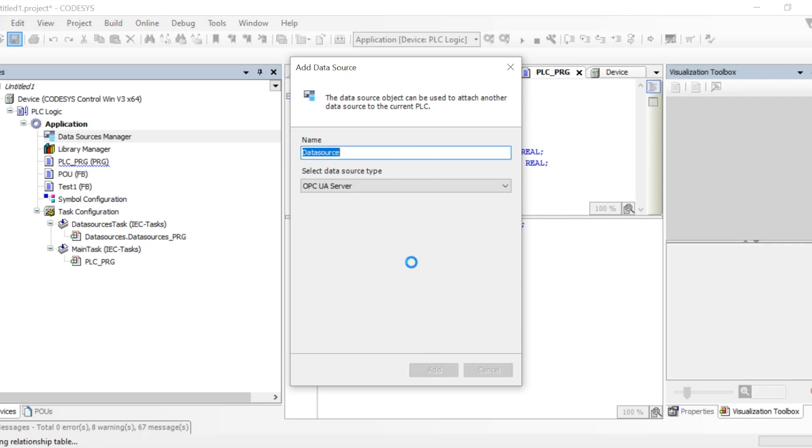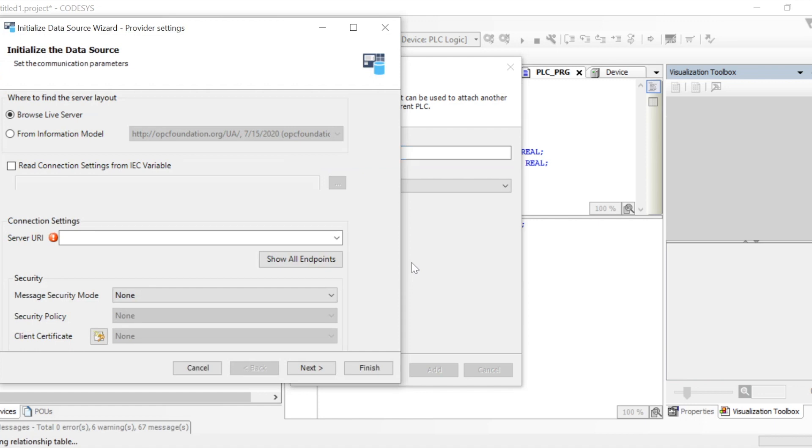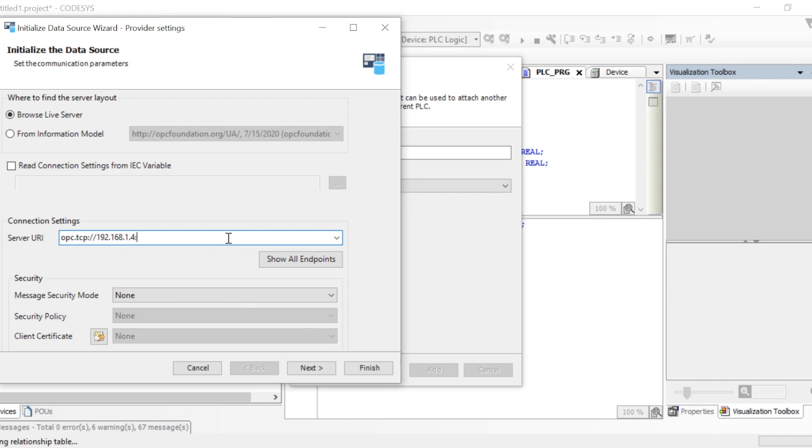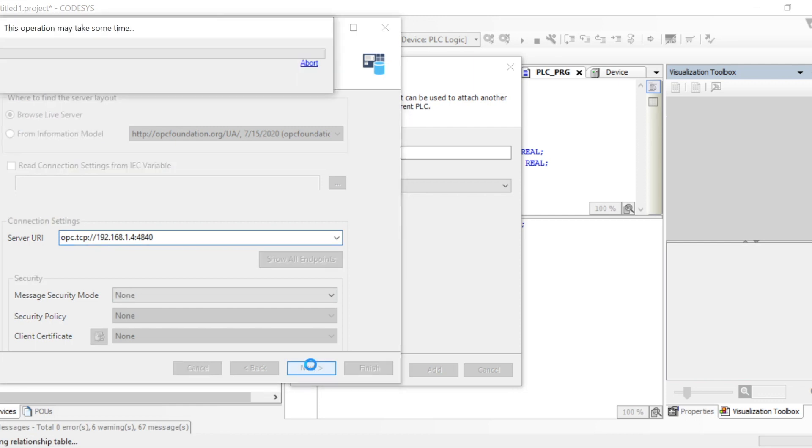When we click on Add, it will take some time to load the Data Source Manager for the OPC UA server window. Here we need to provide the server URI, which means from which server we want to connect. We give the URI link: opc.tcp with the IP and port number. We can also set the security pattern, then click Next.